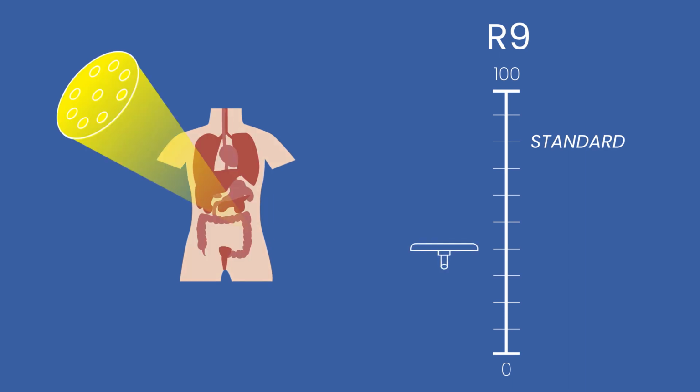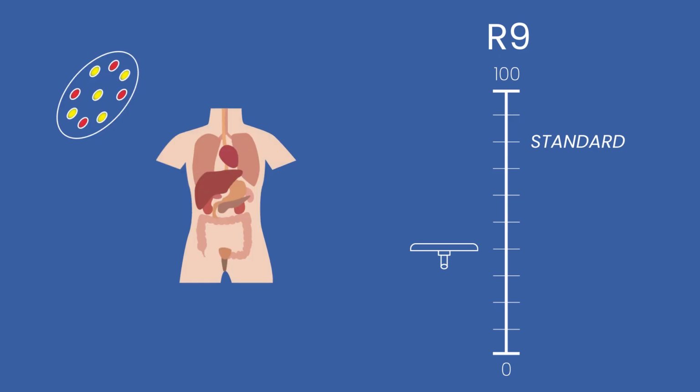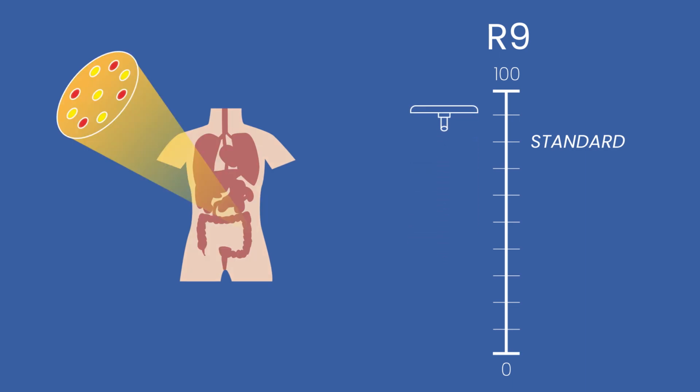Let's consider the example of an operating room lamp, which generally falls short in terms of the standard color rendering value, specifically regarding the value for R9. However, this value can be easily enhanced by incorporating red LEDs, thereby significantly improving the color representation on paper. Unfortunately, this improvement comes at the expense of the actual color rendering of the lamp.